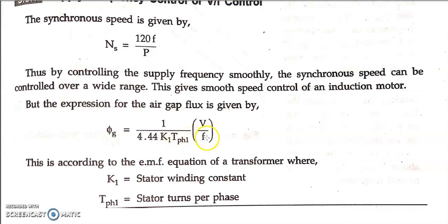So if I'm changing the frequency, what happens? The air gap flux gets severely affected. So in order to maintain the air gap flux constant, what do I need to do? Change the voltage parameter also. And how will I do this? Very simple. Make sure the value of V by F is always maintained constant, no matter whether you increase or decrease the frequency.